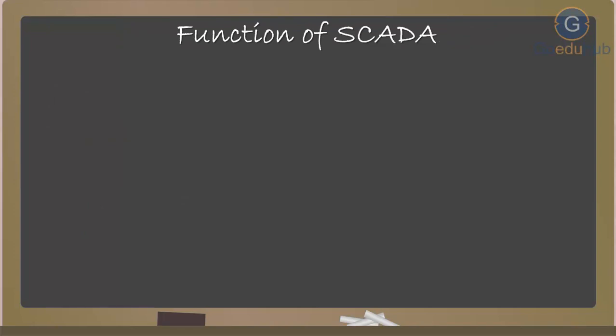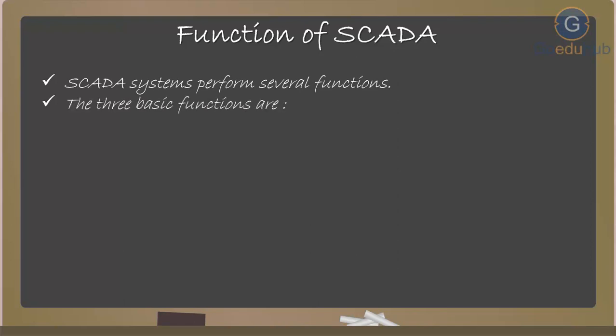SCADA systems perform several functions. The three basic functions are: first, monitoring — which collects data and sends it back to the central computer; second, control — which gathers data from monitoring sensors, processes it, and sends control signals back to equipment according to a prescribed software program; and third, user interface — which is often a large control room where individuals can monitor SCADA input and output responses in real-time.